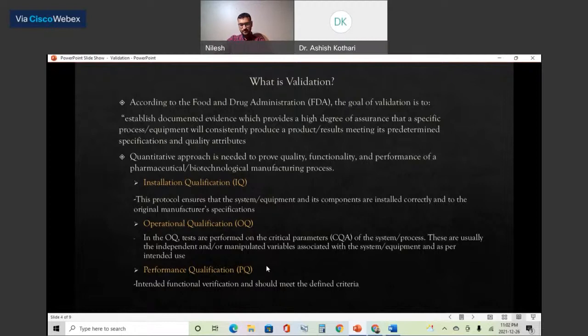In PQ, performance qualification, you identify its consistency. You operate the machine 24/7 for a week, and it should give you the same performance. It should not automatically reduce its speed, temperature, or quality. So for IQ, OQ, PQ, few companies and few equipment do IQ and PQ all together.